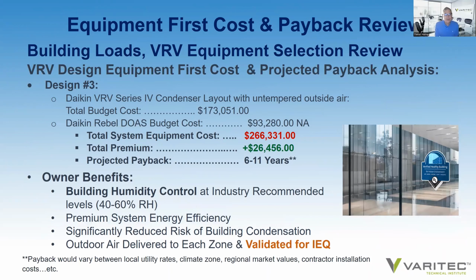Design number 3 is a little more money because the DOAS unit to supply 48-degree dew point air has to be increased in size. Total cost is $266,000 at a premium of $26,000 and a payback of 6 to 11 years. However, in providing this deep dive in lower dew point temperatures on your supply air at 48 degrees, you can now control your building humidity between the 40 to 60% range advocated by ASHRAE and the CDC for reducing the risk of infections in buildings and creating healthier environments.